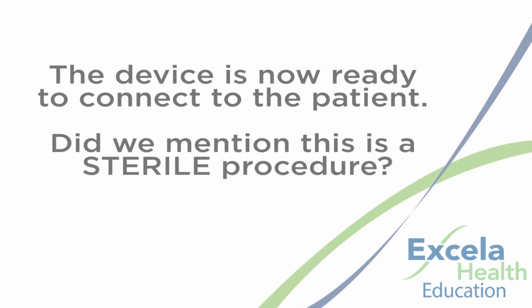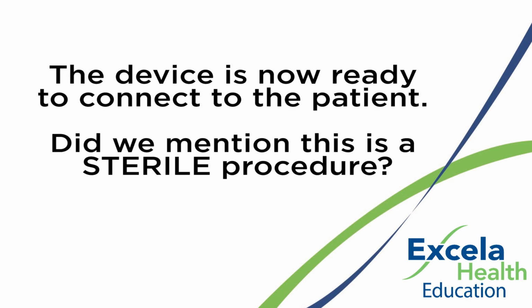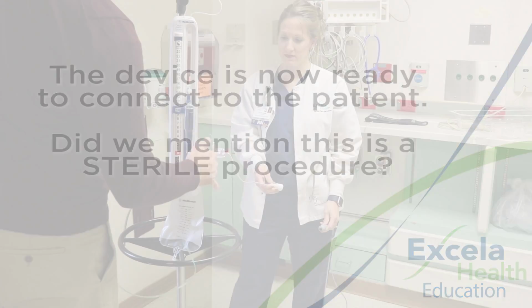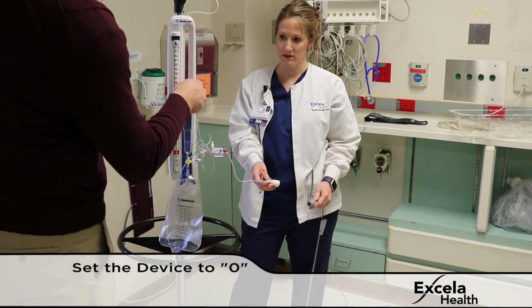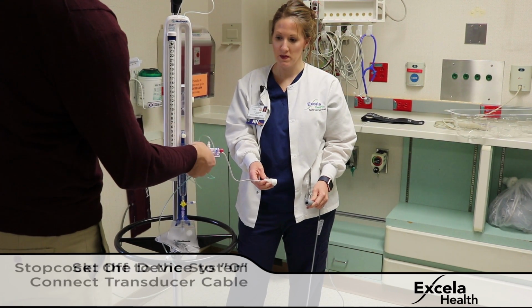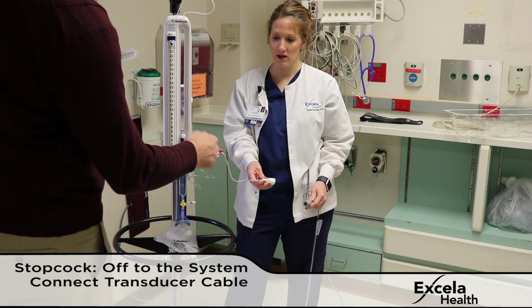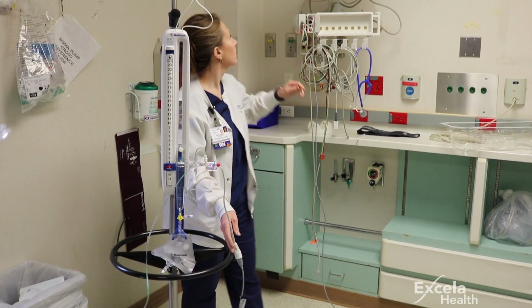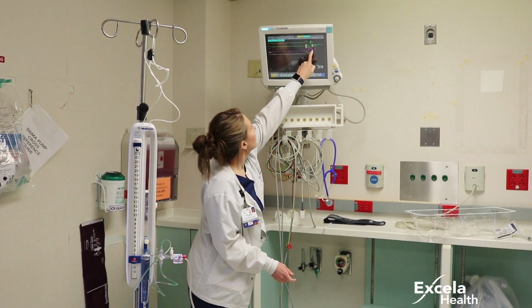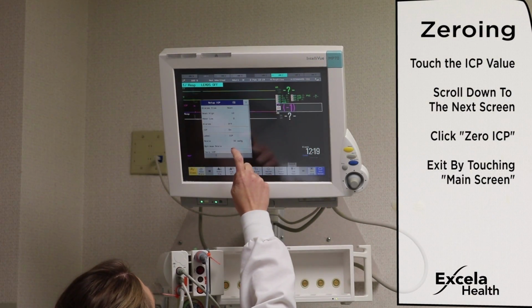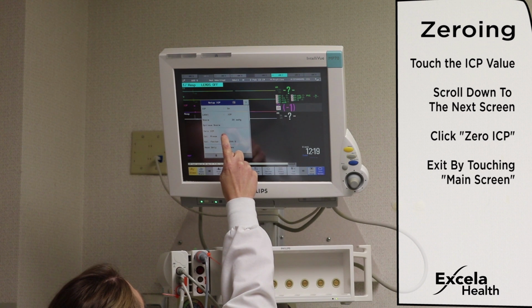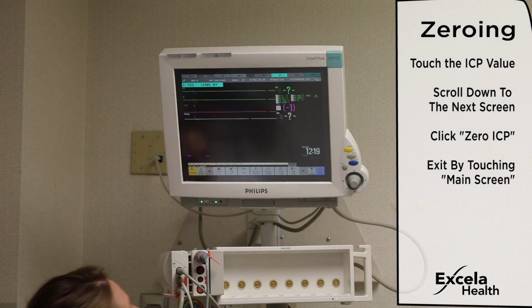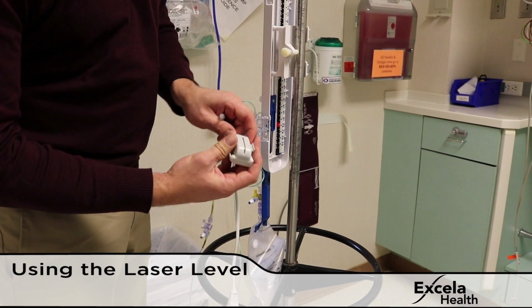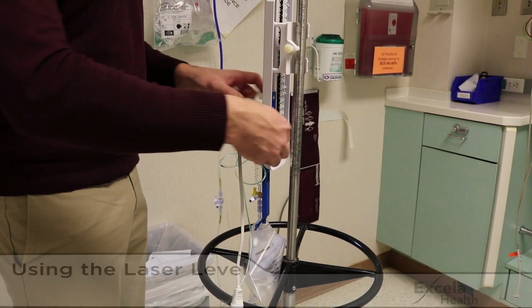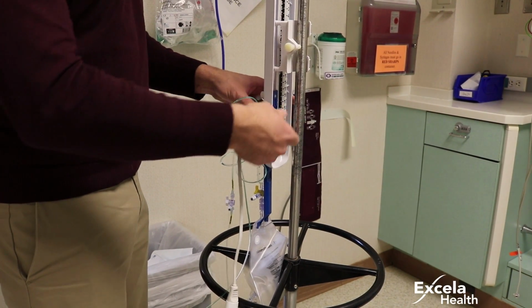Okay. The device is now ready to connect to the patient. Once we have everything connected to the patient and we have the system set down at 0, we're going to turn the main system stopcock off to the system. We're going to connect the transducer. And at that time, you will push the 0 button. There's a button you push on the clamp here, and it clamps onto the back of the main system stopcock until it clamps on.